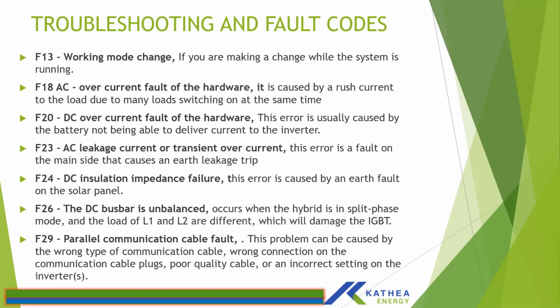And then DC insulation impedance failure. This is a common fault. This is mainly caused by low resistance between your PV strings and ground. So usually you just need to measure your PV strings and make sure none of your PV strings is shorting with ground, like that is positive to earth, and then negative to earth.